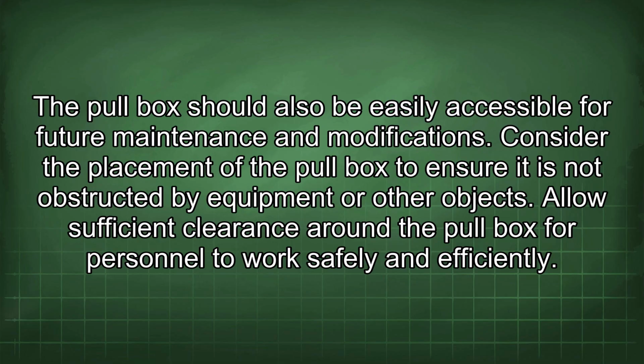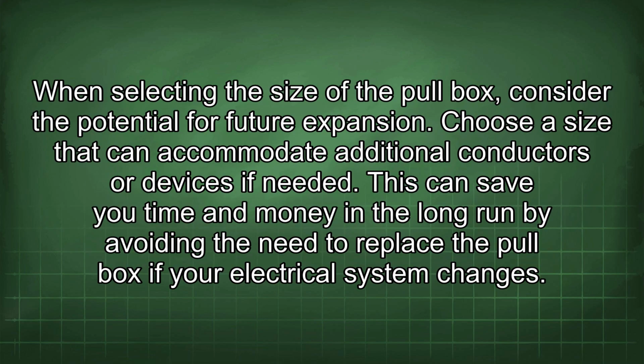The pull box should also be easily accessible for future maintenance and modifications. Consider the placement of the pull box to ensure it is not obstructed by equipment or other objects. Allow sufficient clearance around the pull box for personnel to work safely and efficiently. When selecting the size of the pull box, consider the potential for future expansion. Choose a size that can accommodate additional conductors or devices if needed. This can save you time and money in the long run by avoiding the need to replace the pull box if your electrical system changes.